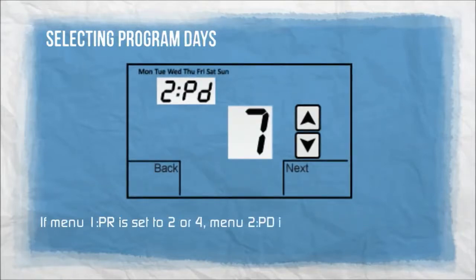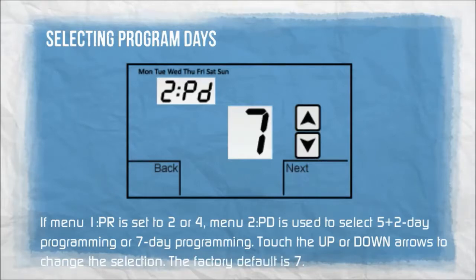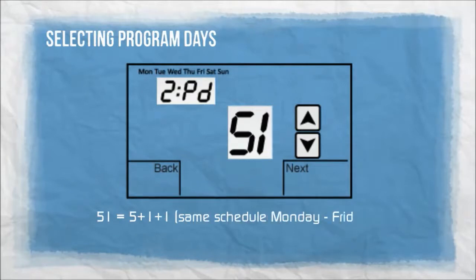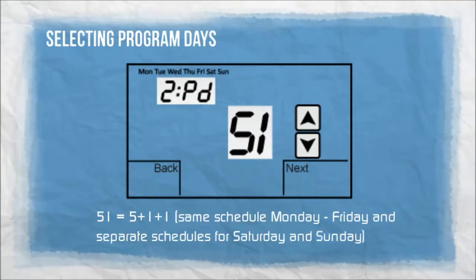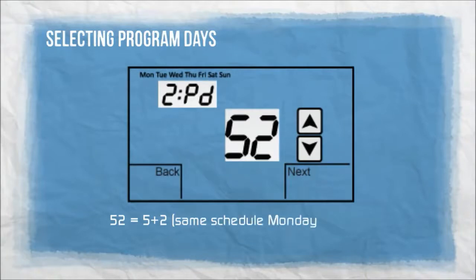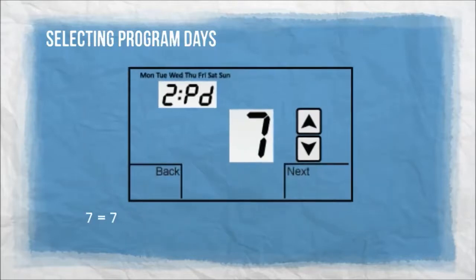If menu 1PR is set to 2 or 4, menu 2PD is used to select 5-plus-2 day programming or 7-day programming. Touch the up or down arrows to change the selection. The factory default is 7. 5-1 is for 5 plus 1 plus 1: same schedule Monday through Friday and separate schedules for Saturday and Sunday. 5-2 is for 5 plus 2: same schedule Monday through Friday and Saturday through Sunday. 7 equals 7-day programming, individual programming for each day of the week.